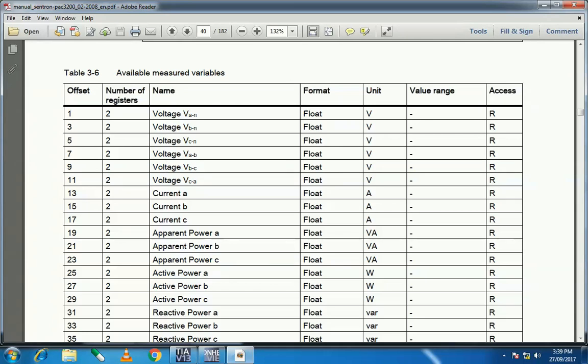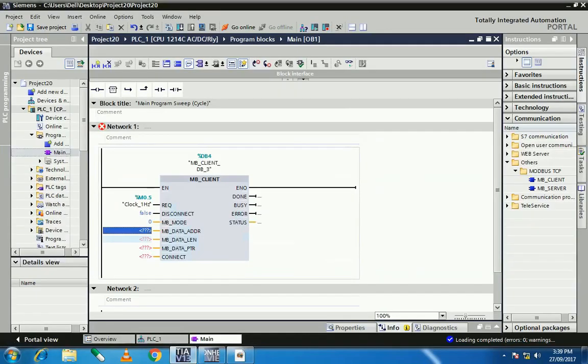The offset is one, and we are using the holding register. The holding register starting address area is 40000. Since 40001 is the base address and the offset is one, the first starting address is 40001 plus one, which equals 40002. So here I set 40002.